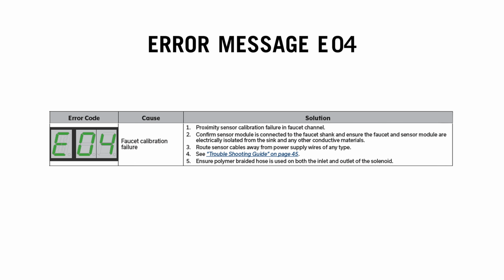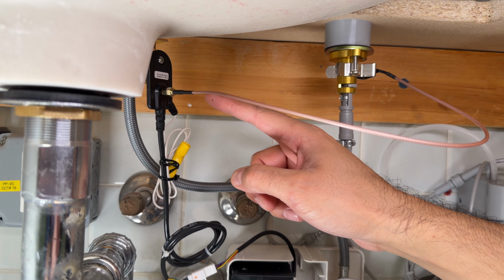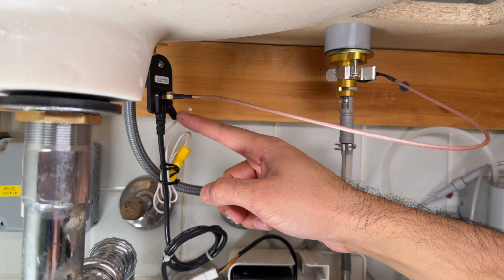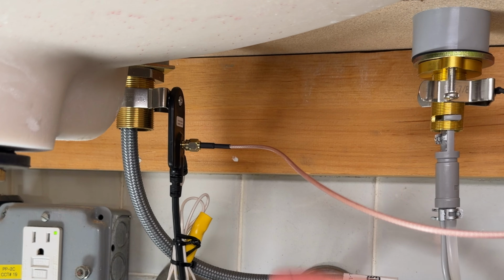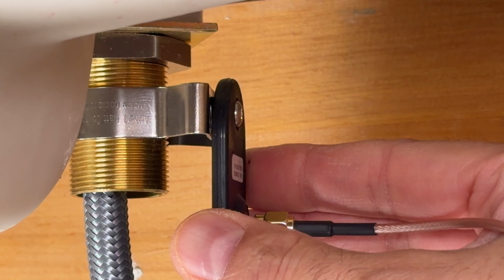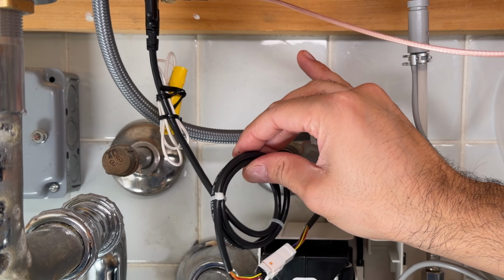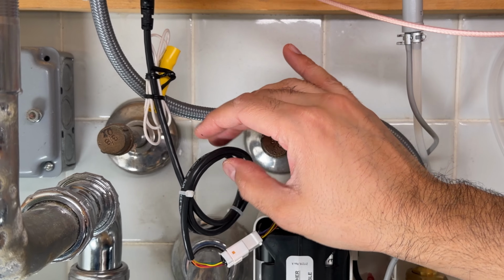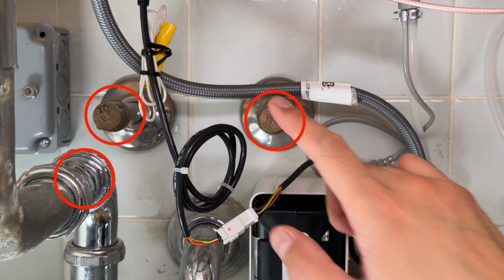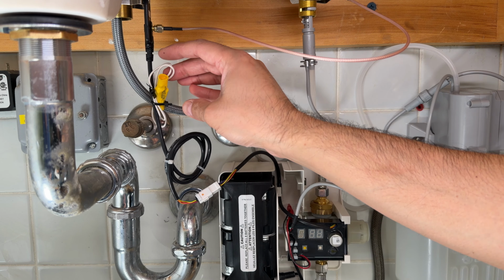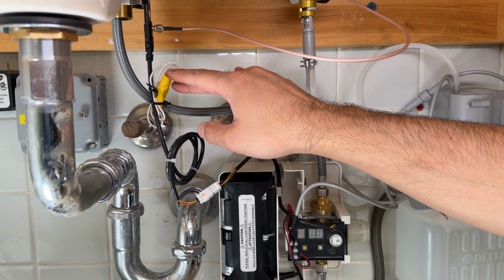This could mean many things. For example, the proximity sensor calibration failure in the faucet channel. Confirm that the sensor module is connected to the faucet shank and ensure that the faucet and sensor module are electrically isolated from the sink and any other conductive materials. If the surface is conductive, ensure you're using the grounding wire from the sensor and grounding out the surface.